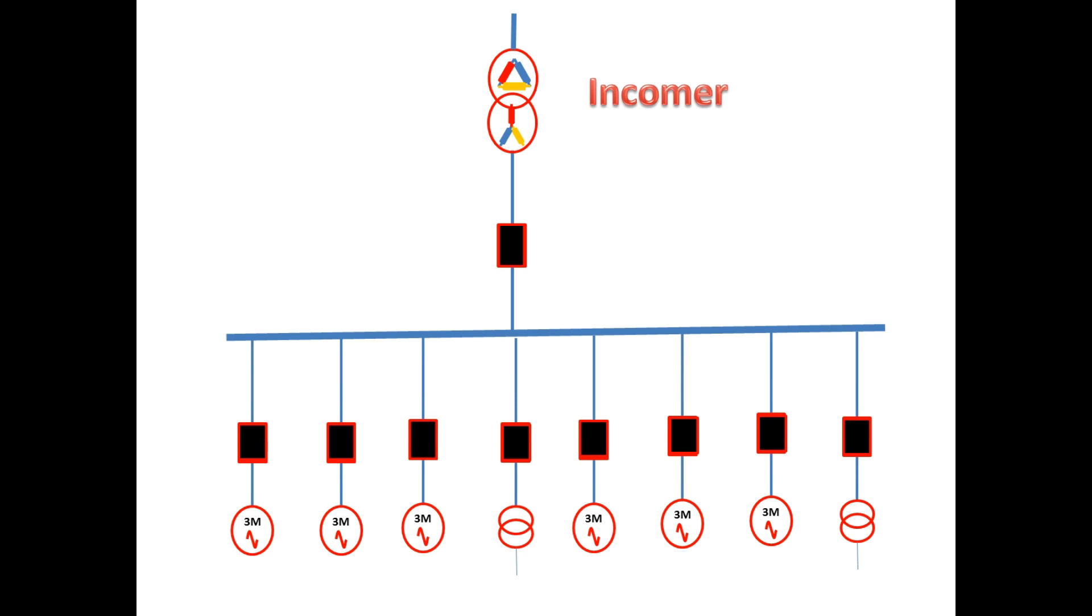Let us consider this is incomer, it connects with bus and bus has many outgoing feeders. All these outgoing feeders are load for incomer. Considering each taking 40A as its full load current for each feeder. So the incomer will take 320A as load current and also we are considering the incomer transformer full load current as 320A.